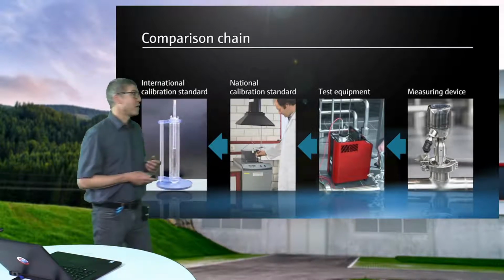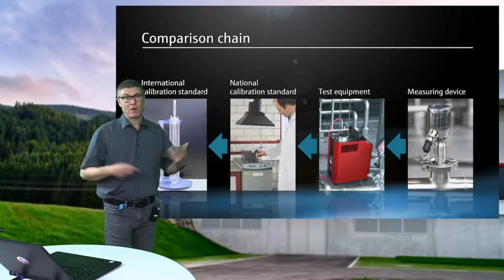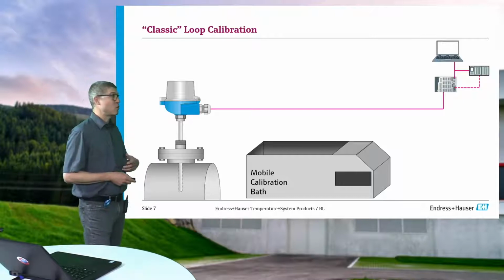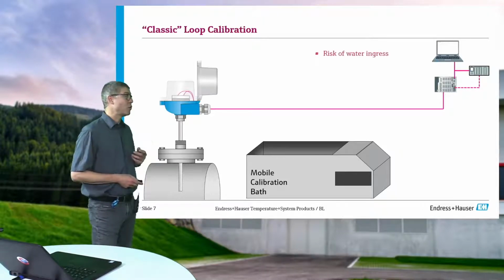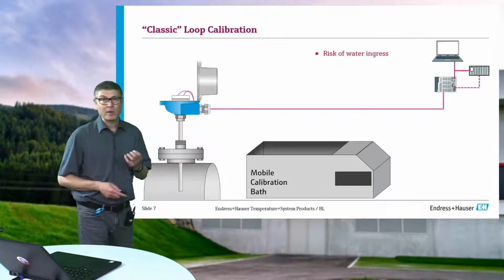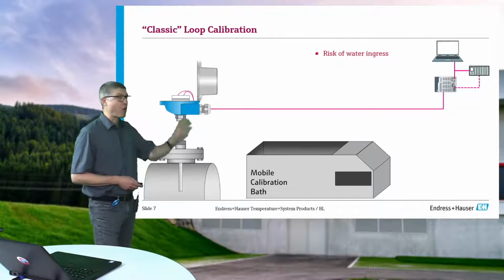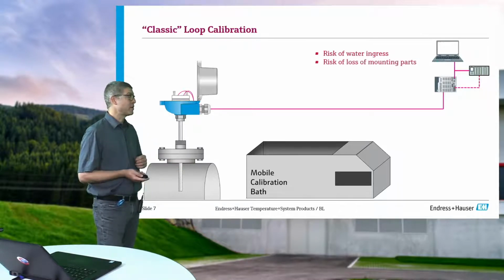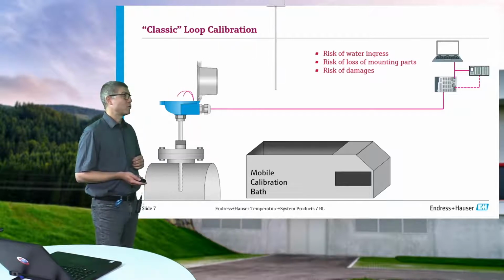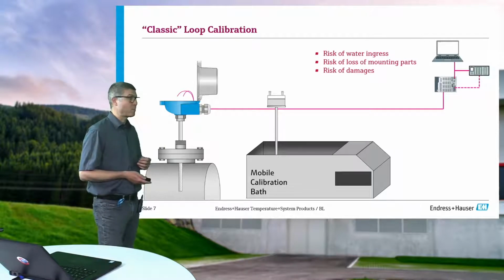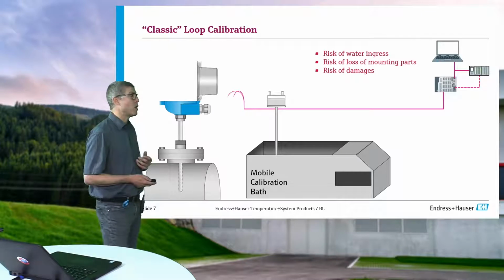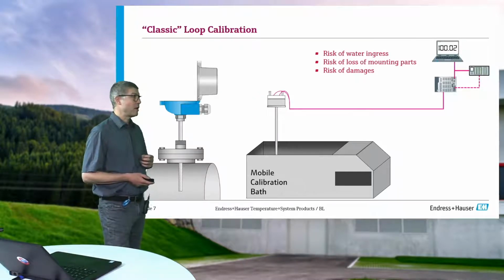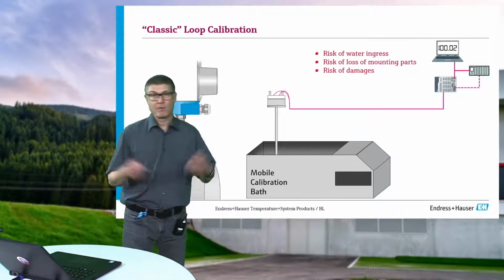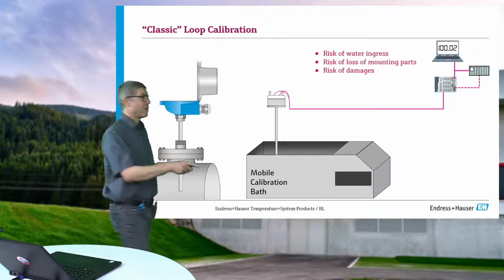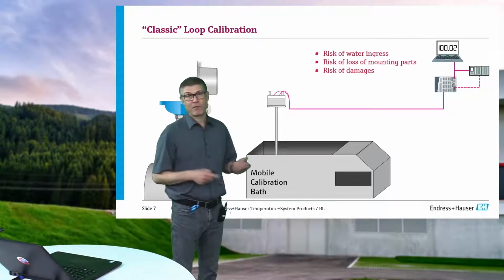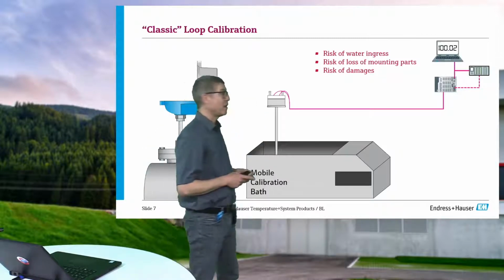So a standard, classical or traditional calibration works like this: you go into your plant and you dismount your temperature sensor. Usually you only take out the measuring insert, so the thermowell stays in your process. That means you disconnect the wires, you carry the measuring insert to your calibration bath, and to do the calibration of the complete chain, you have to reconnect the wires to the measuring insert, and then you go to several temperatures, for example 3 points, and check if, for example, when you go to 75 degrees Celsius, it is really shown in your process control system.